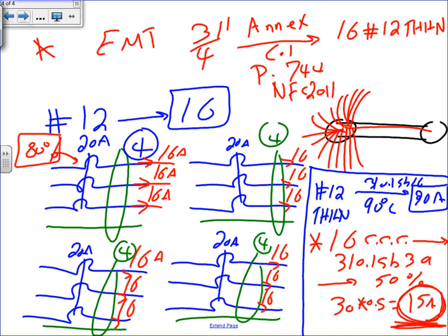As long as, in my humble opinion, the conductors are number 12 and the overcurrent protection device is a 20 amp, whatever load, it doesn't matter what you're feeding. Group them. As long as you're using number 12 and a 20 amp breaker. By the way, do we use number 14? If I hear you, Rob, my friend, saying number 14, I will pick a fight with you at the end of the parking lot. I'm not going to win, but I'll take my chance. So a number 14 conductor and 15 amps, Ashley, you open that window and bundle them and throw them out. Don't use number 14 and don't use 15 amps in a commercial building.